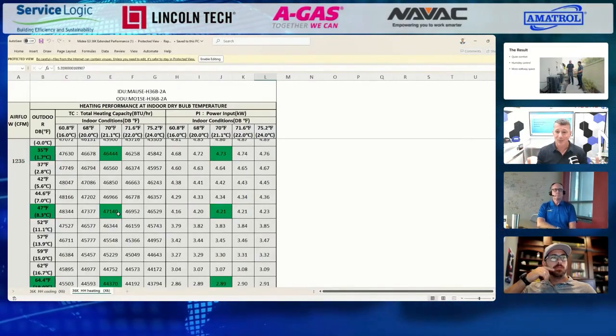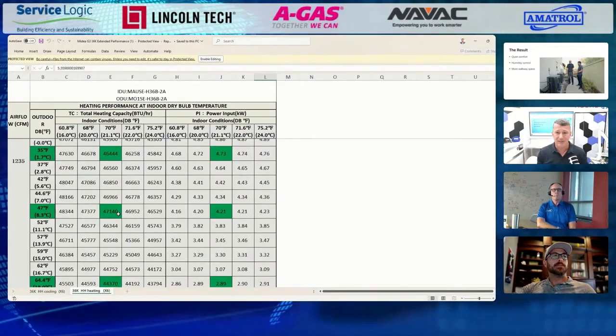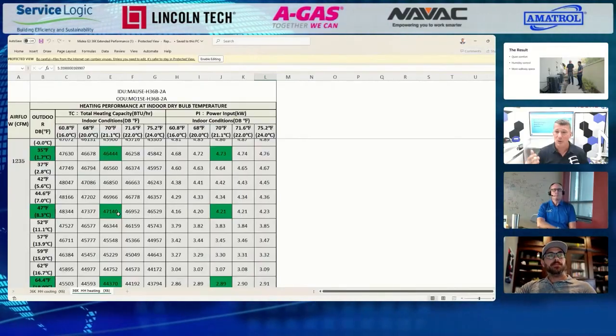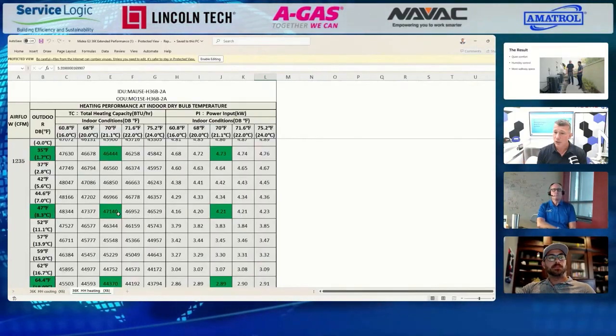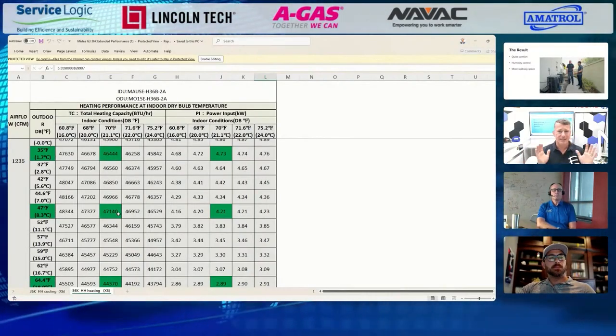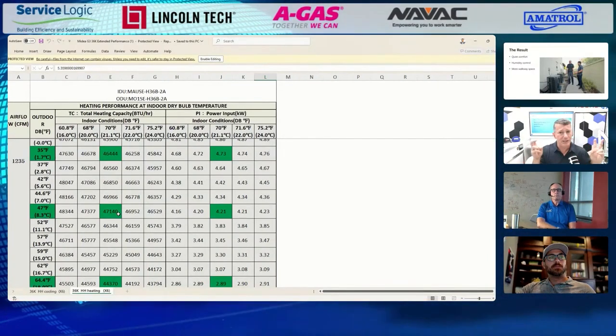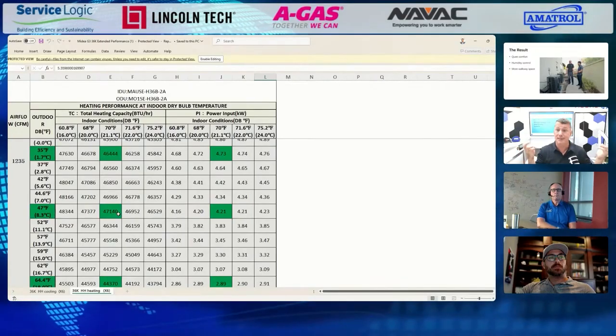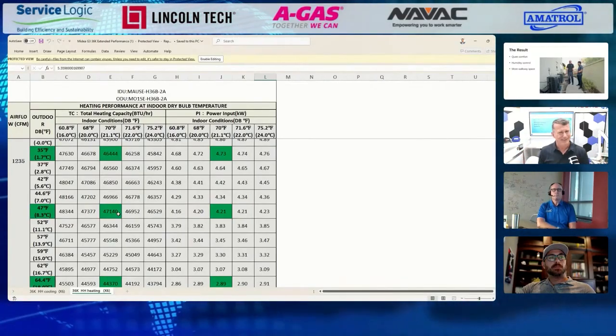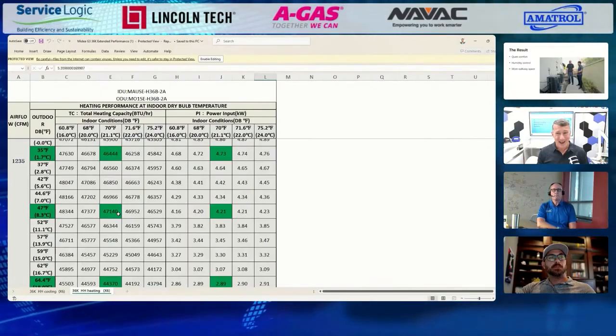We have to look at what is the BTU capability of this thing in heating mode and cooling mode at different parameters. Because you'll find systems in that tonnage range, and then if you look at their heating at 47 degrees, you go, oh, it's in that tonnage range. Is that a good thing or not?